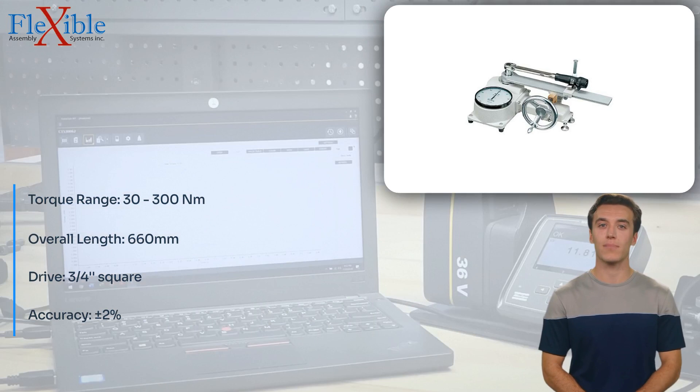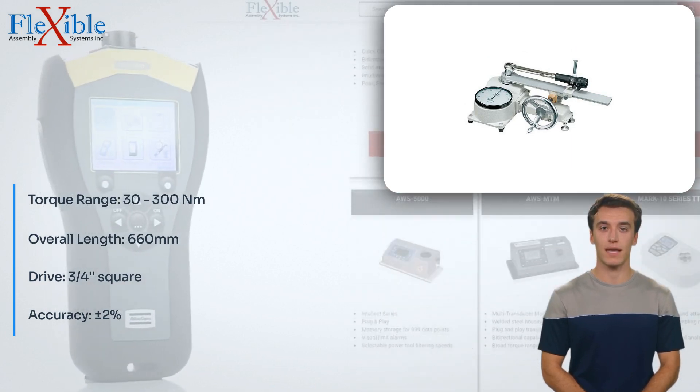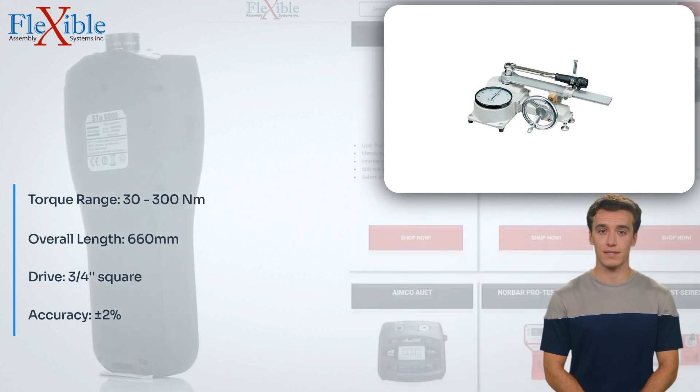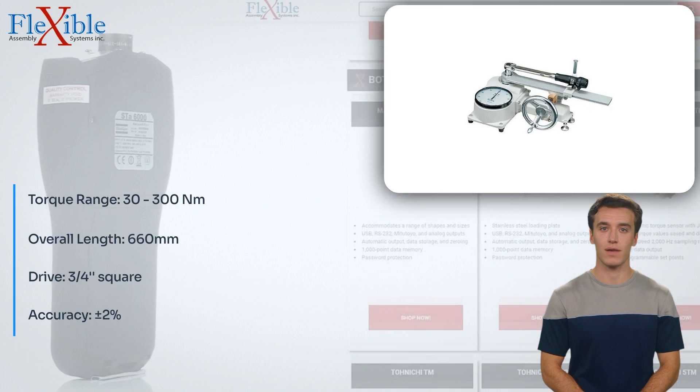Designed to be set horizontally, the D300N eliminates the need for weight correction, simplifying the testing process. Trust in the Tohnichi 300N torque tester for precise and reliable torque measurements, making it an essential tool for quality control professionals and technicians across various industries.